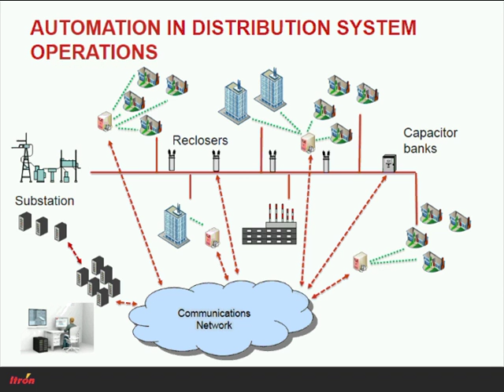Before going further, I want to talk about different types of distribution systems within the grid. Radial systems are pretty prevalent, especially in rural areas, where loads are located along the line moving out from the substation or source of power, and located laterally along the line. Ring or loop systems have service loops through the service area that tie back to the original source, containing a substation and often some alternate generation so customers can be provided with power in either direction.